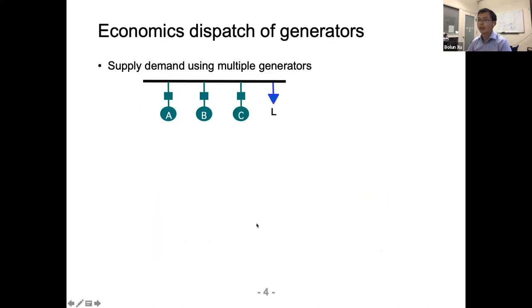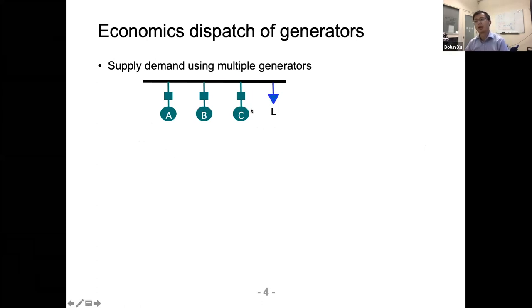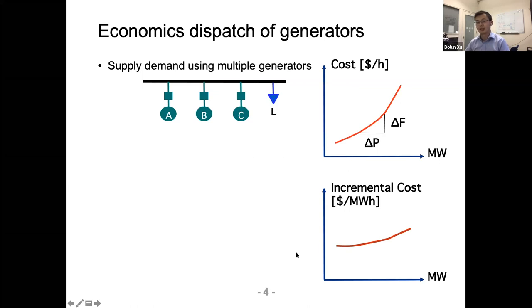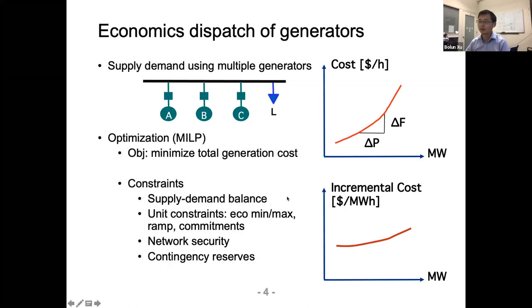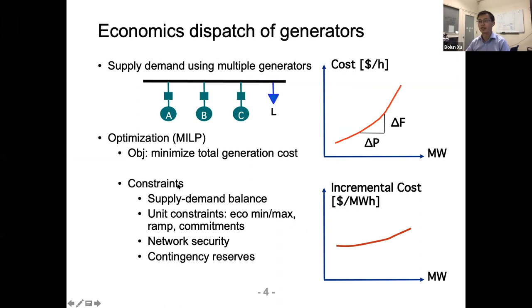Let's review what economics means in power systems. The most basic concept is economic dispatch: figuring out how to use multiple generators to meet demand. Each generator has a cost curve and incremental cost. We formulate this as a linear or mixed-integer linear programming problem — minimize total generation cost subject to supply-demand balance, network security, and other constraints. This is the traditional generator-based dispatch framework.